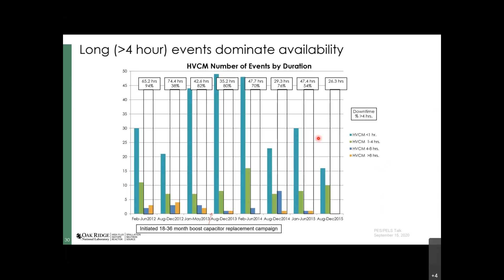So a large number of events, but short duration, all the way to the events in orange, which resulted in downtime greater than 8 hours. In the box, you see the number of hours associated with that run period total. And then the percentage in the box is the percentage associated with downtime that's in excess of 4 hours. So you can see in almost all cases, the 4-hour events are responsible for about three-quarters or more of the downtime. Those are the things that we focused on, and those are the things that we continue to monitor.